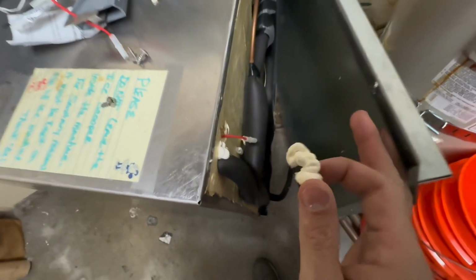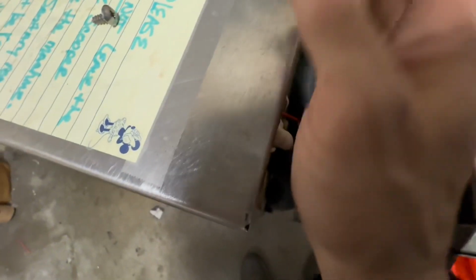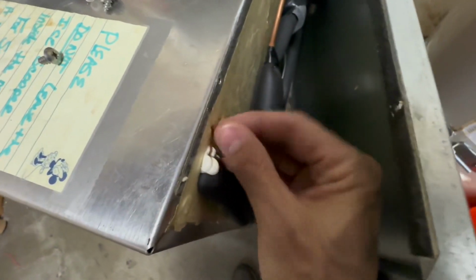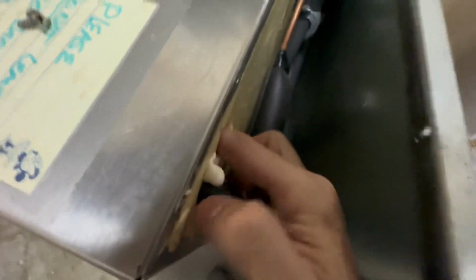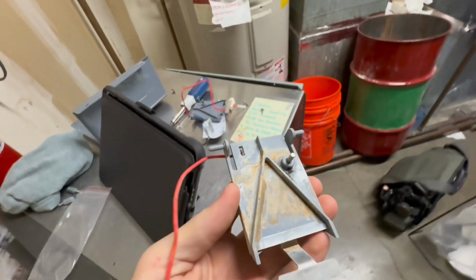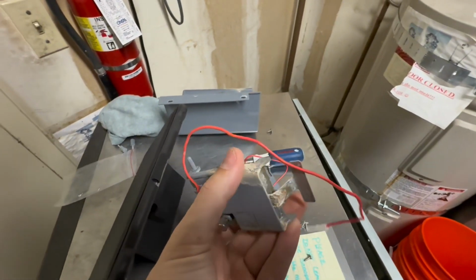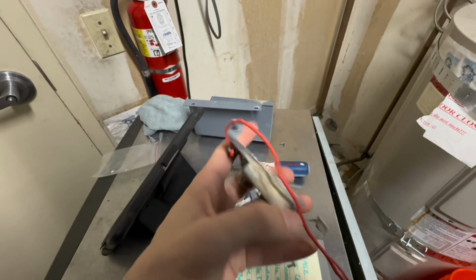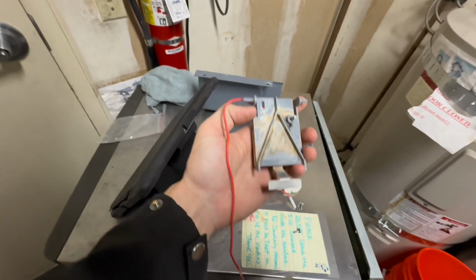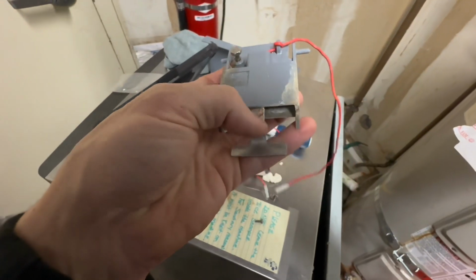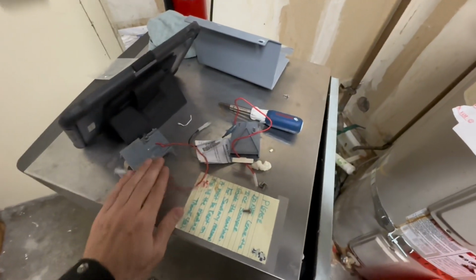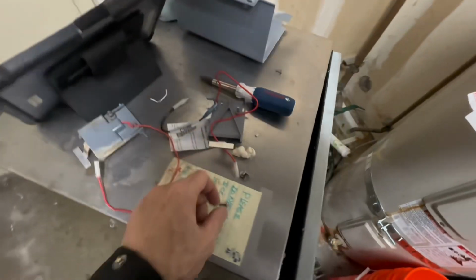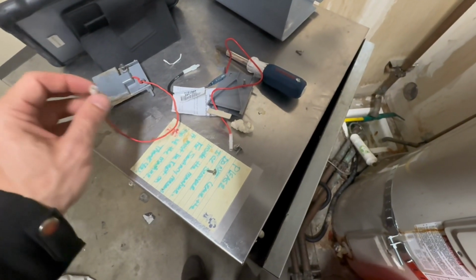There was this piece of silicone that was shoved inside that hole. I just ripped that out, and then this will get fed in, and then you can go around this side, pinch the ice thickness probe from the left, pushing it to the right, and that'll come out just like that. And some of this calcium buildup on here, when it gets wet, it can ground itself out. And yeah, I could scrub on that and scrape on that, but replacing it is a sure shot way of taking care of the issue.